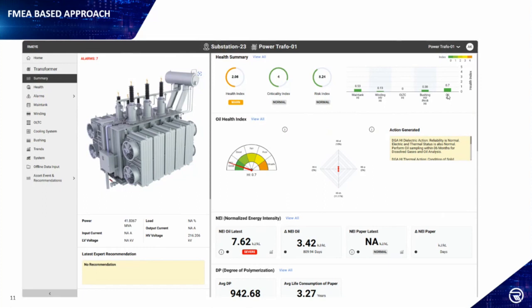But we need to factor the oil regeneration that has happened into the transformer. So how do we factor this into the new oil health index represented after regeneration? Definitely, the health index will improve after regeneration, but not as much as a new transformer with similar gas composition. This kind of data is very important to consider when coming up with the health index or risk index calculation of a transformer.